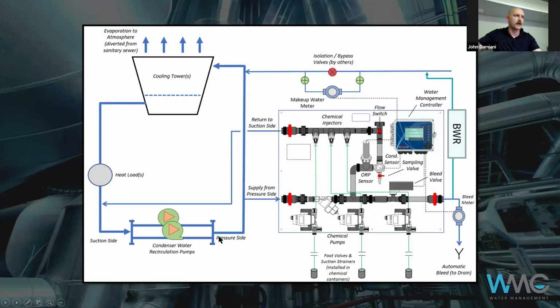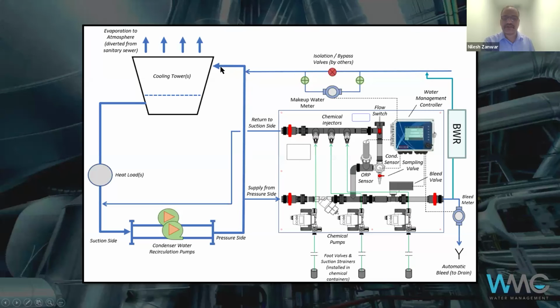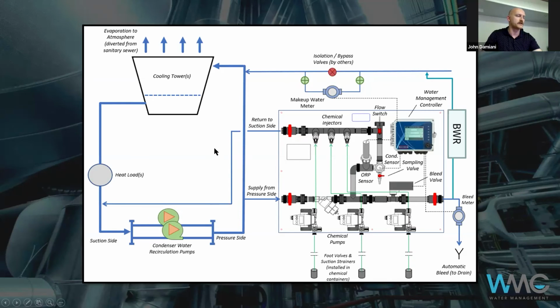So the water that goes through here is basically a closed loop. It's inside tubes. So there is treatment. And is this loop on your system water, or is it like a glycol? No, it's an effluent treated water, not glycol. Okay, so it's treated water. So anything that runs in a closed loop, the downside of an open system is that you're making up water into the system, so it uses water. But the benefit is you're able to reject water, so you can keep it clean in that sense by draining the water. A closed loop has to recirculate the same water over and over.